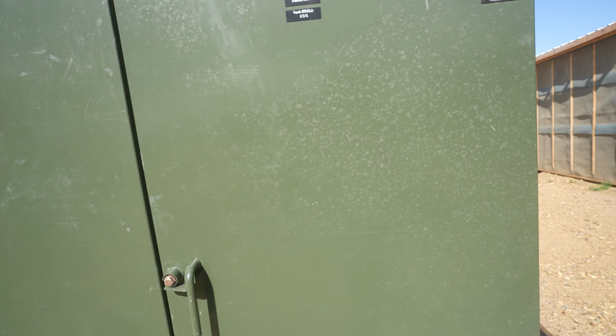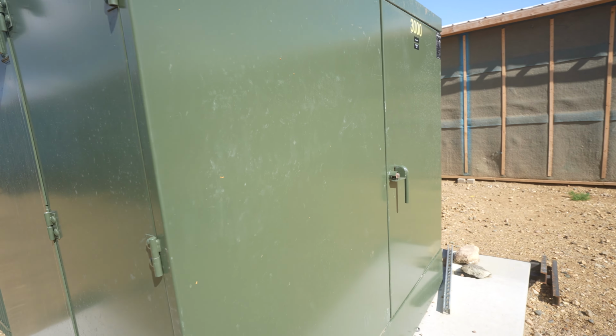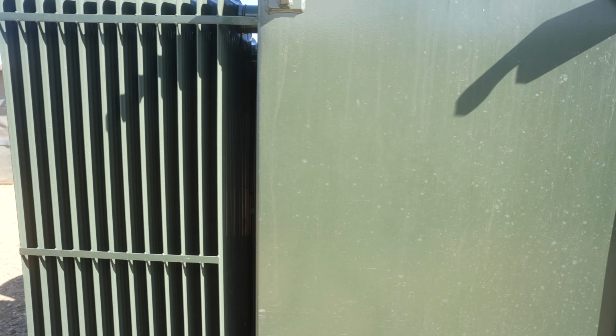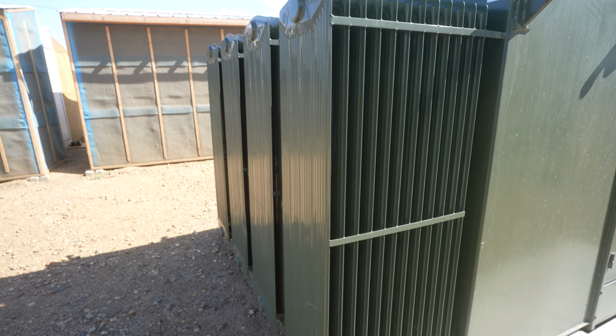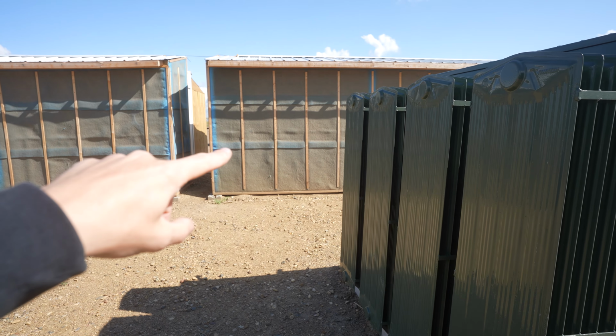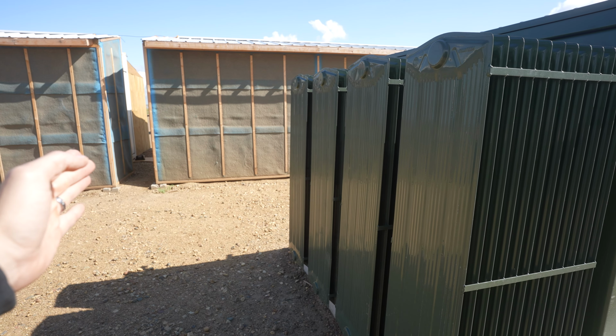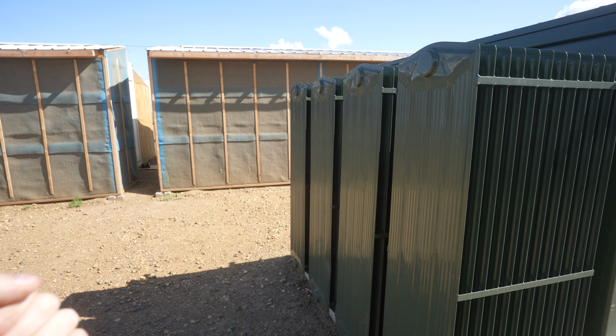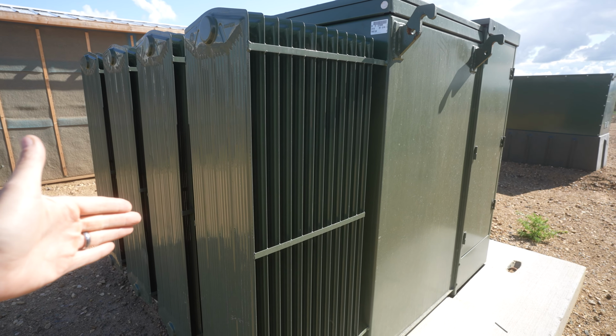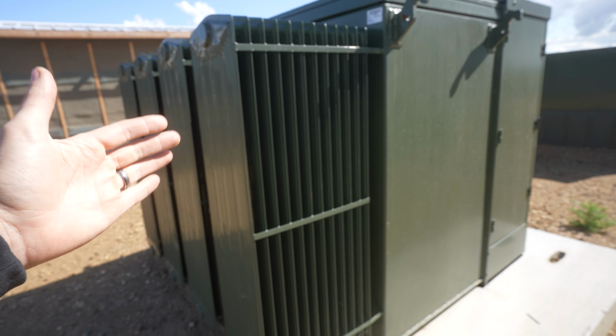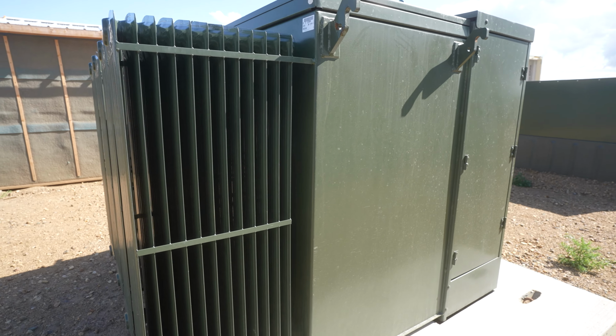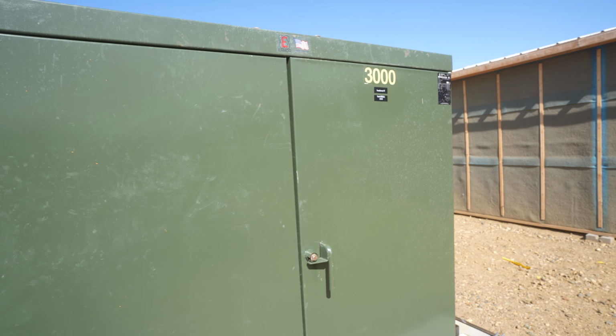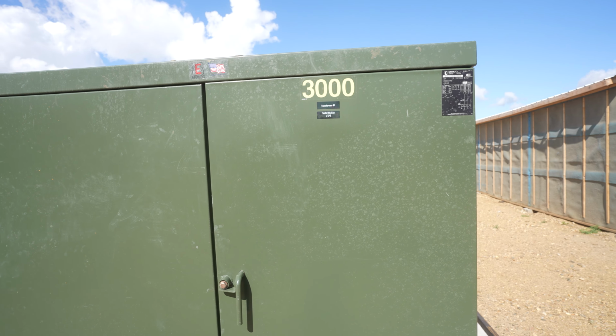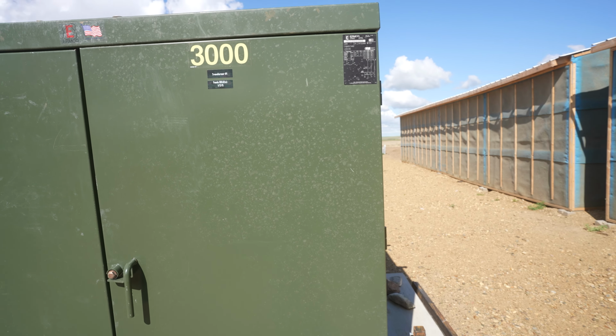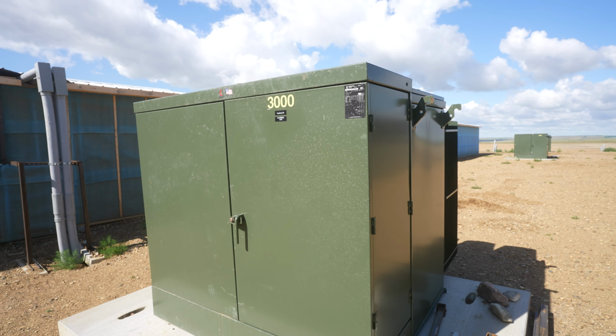This is a 100% loadable transformer, so we can put all 3 megawatts on it immediately. It's also built to withstand 110-120%, which means during summertime, if a container goes from 1 megawatt to 1.1 because of the heat, it doesn't matter. If you load another 300,000 on top, going from 3 megawatts to 3.3 megawatts, it can still handle all of that. It's built that way, and we got these transformers specifically for that reason, to make sure we can handle those hot summer days. That's our brief overview of the transformer.